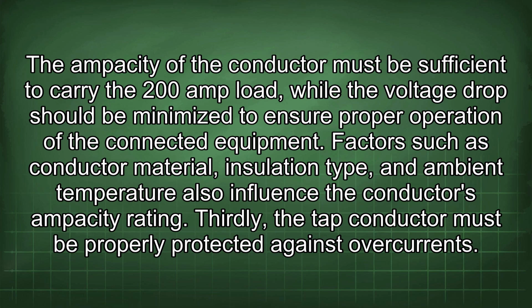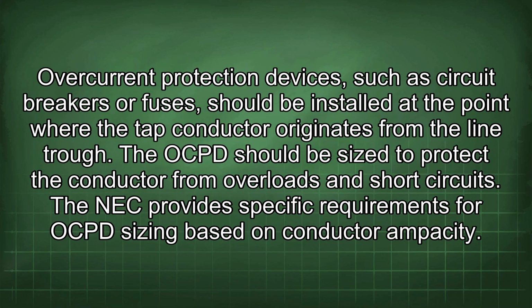Factors such as conductor material, insulation type, and ambient temperature also influence the conductor's ampacity rating. Thirdly, the tap conductor must be properly protected against overcurrents. Overcurrent protection devices, such as circuit breakers or fuses, should be installed at the point where the tap conductor originates from the line trough. The OCPD should be sized to protect the conductor from overloads and short circuits. The NEC provides specific requirements for OCPD sizing based on conductor ampacity.